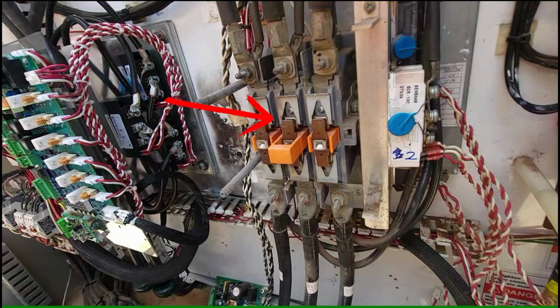And so you'll have a transition process between the SCR and the electromechanical starter. But again, we gently bring the motor in, which is the soft starter part of the solid state. But the solid state component of this is the SCRs. This is what makes it solid state, versus a Y delta starter, which uses 3 of these starters to accomplish a similar effect, but we do it by reconfiguring how the motor windings are configured, going from a Y configuration to a delta.